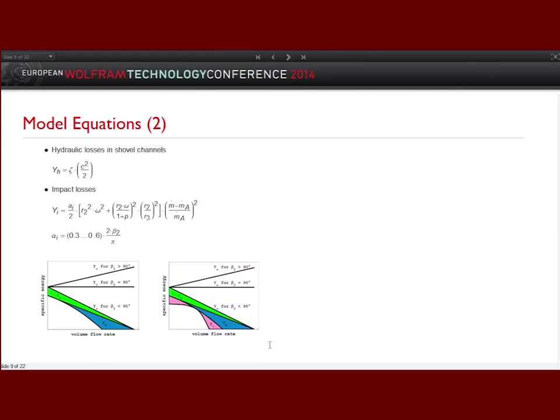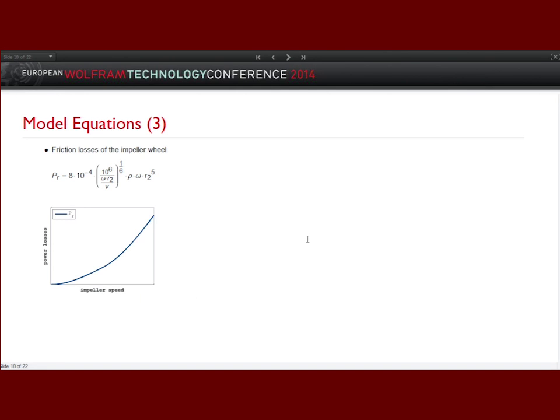The next step is to identify hydraulic losses in flow channels between the blades in the water pump, then impact losses. You can see on the picture the characteristic line of this water pump, and between are the losses in the flow machine. Then, to identify friction losses of the impeller between impeller and housing of the pump — it is easy to find and implement this equation. You can also see the power losses versus impeller speed.